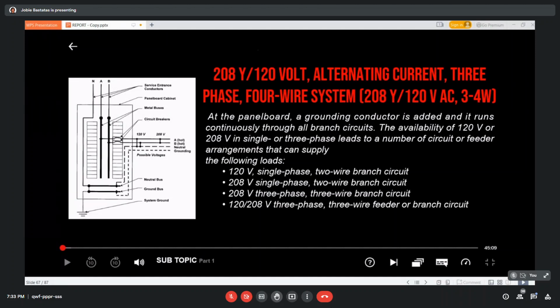The availability of 120 volts or 208 volts in single or three phase leads to a number of circuit or feeder arrangements that can supply the following loads. First is the 120 volt single-phase two-wire branch circuit. Next is the 208 volt single-phase two-wire branch circuit. 208 volt three-phase three-wire branch circuit, and 120/208 volt three-phase four-wire feeder or branch circuit.